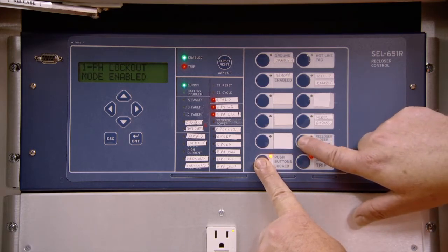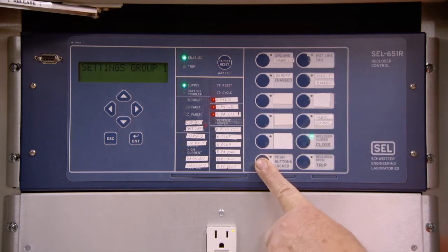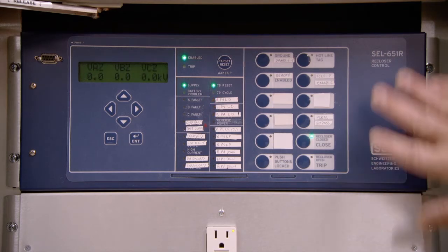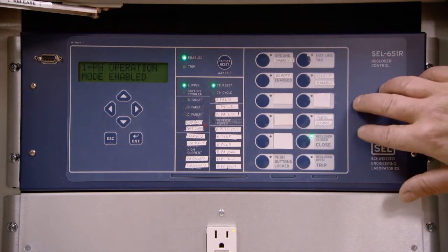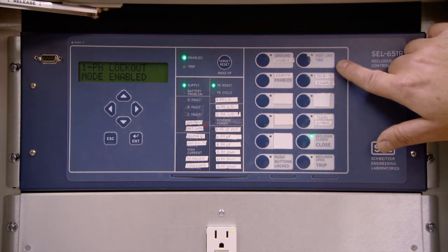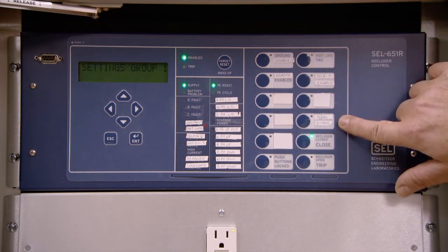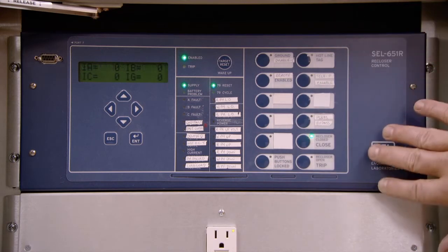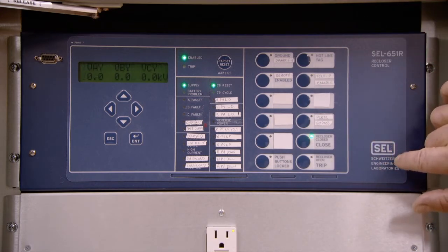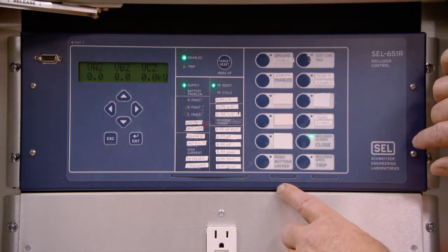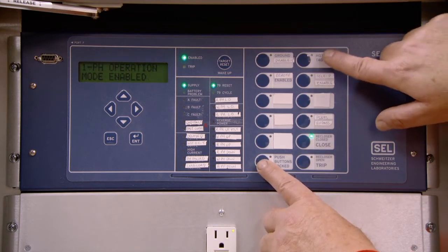Any other buttons on the panel, such as the ground, hotline tag, teleprotect, permissive bypass, or remote enable, will also have to have the master lock or the push buttons locked button pushed at the same time as those buttons to activate the feature. If you don't, you'll not have any functionality from any of the buttons on the panel.